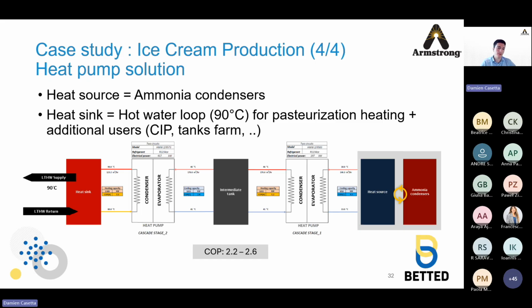By the way, you can have different projects where that intermediate temperature level at 50 could be used for other needs, such as building heating. So that's a smart way to lift heat efficiently and with possibility to have some flexibility as well. And then that comes with a COP of 2.2, 2.6, depending on the details. And that basically is way more than one.